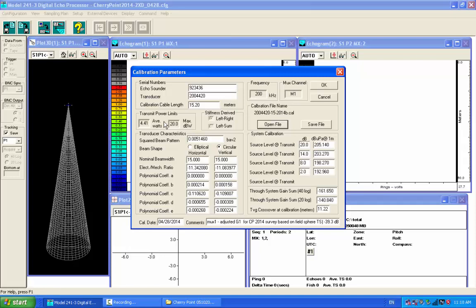But this one, it is starting to tail off, mainly on real high frequency transducers and the big high powered echo sounders. You might see points where you're going up in gain and really just not getting any more power out of the transducer. But I always, on the 241s, run them at 20 dB watts, and then it basically gives the receive efficiency, how efficient the transducer is at converting that pressure wave back into a voltage.